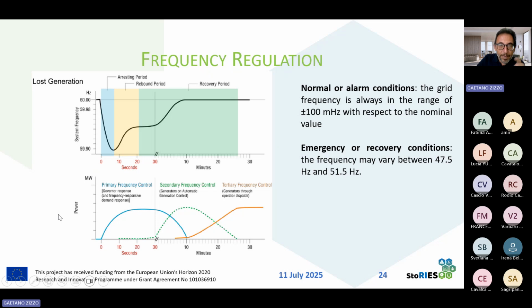This is only a brief reminder that we have primary, secondary, and tertiary regulation, because during a fault, for example, during the loss of generation, frequency decreases rapidly, only contrasted by the governor response and by the inertia of the system. The governor response in this case is activated immediately, and in a first phase that is usually of 30 seconds, the regulation system, the control system of the power plant must contrast the reduction of the frequency. So after 30 seconds, the frequency reduction is contrasted, and the new value of frequency, that is no more the rated one, is reached.